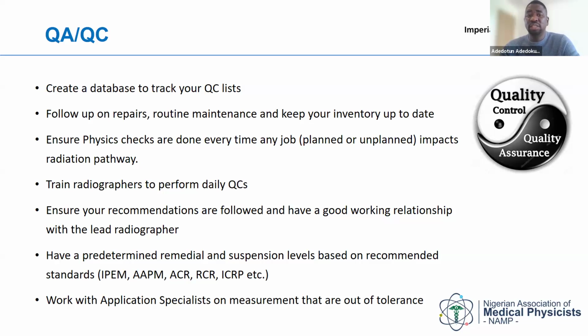You want to be sure that they run the generator test, the constancy test, the kV accuracy. You want to be certain that, yes, the kV is still as accurate as possible. They can't wait for once a year when physics is going to do the check. They do a minimal image quality test also. When you train radiographers, you are just helping yourself. They're not taking your job.